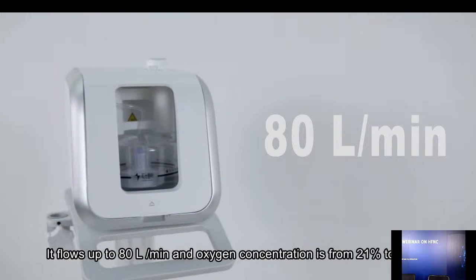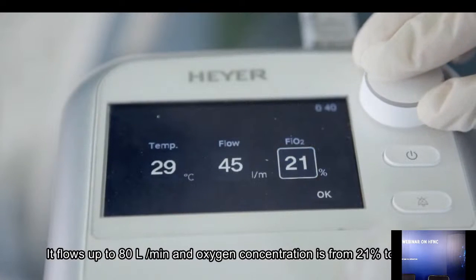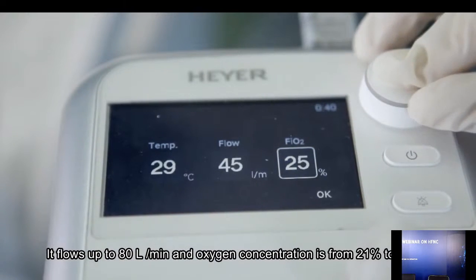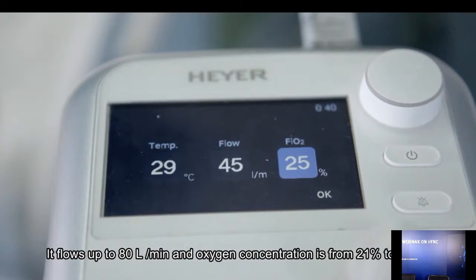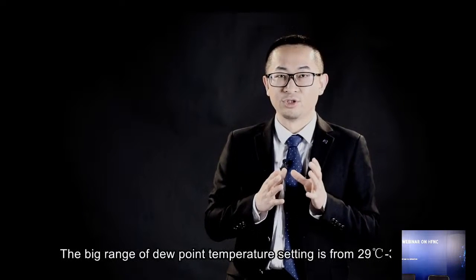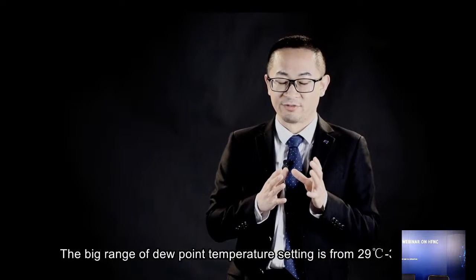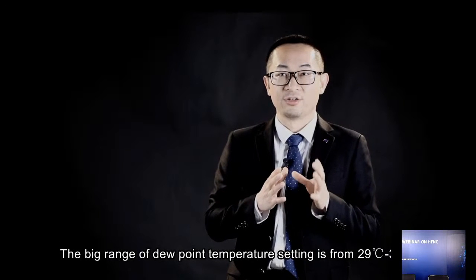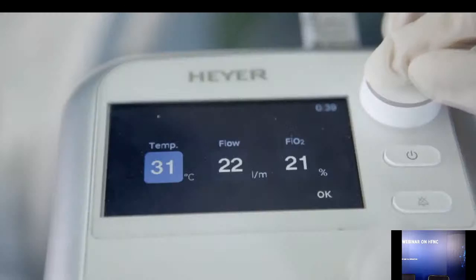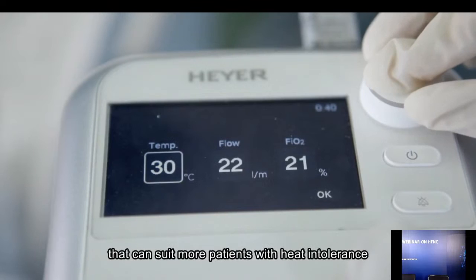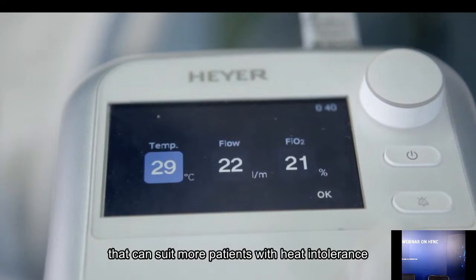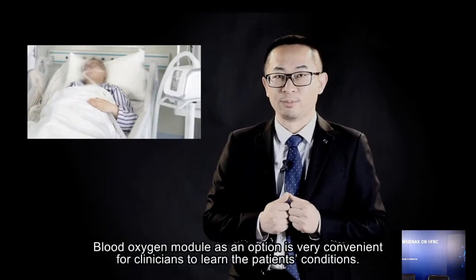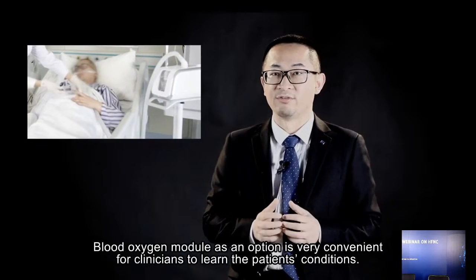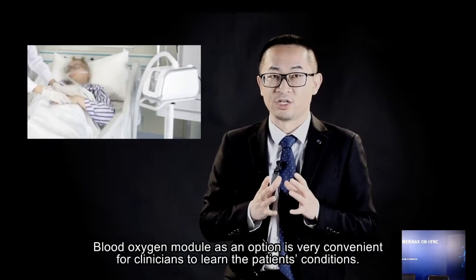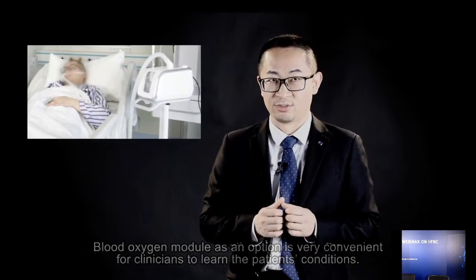It flows up to 80 liters per minute, and oxygen concentration is from 21% to 100%. The big range of dew point temperature setting is from 29 to 37 degrees Celsius that can suit more patients with heat intolerance. Blood oxygen module as an option is very convenient for clinicians to learn the patient conditions.